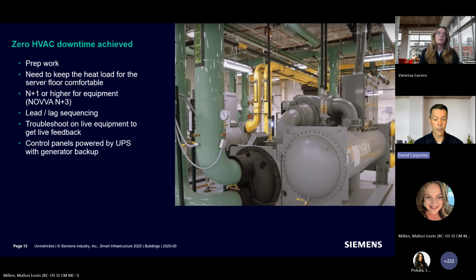And having an N+1 is critical. On this particular site, NOVVA had N+3. And so we could still maintain a lead lag in one chiller plant while having one of the pieces of equipment in the other chiller plant down. That meant that they were able to have a little bit of peace of mind, but during the change out, those were operating on the failing infrastructure, the MSTP network that was giving false alarms, having communication problems.